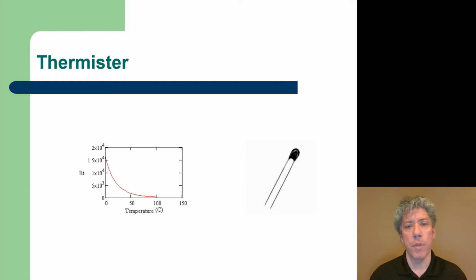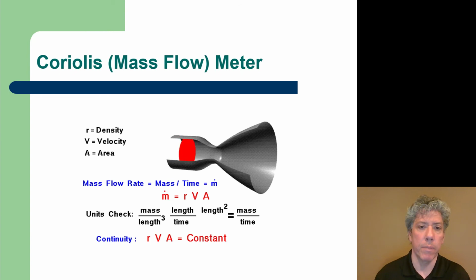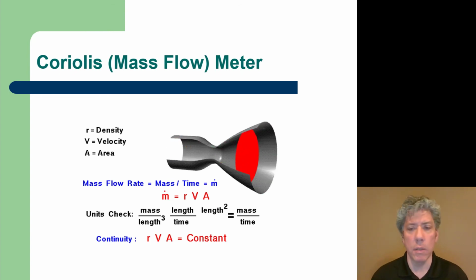There are also thermistors. Now, these are commonly used for sensing reference junction temperatures. They are nonlinear in the sense that their resistance does not vary linearly with temperature like an RTD does. But as long as you can calibrate it and keep a calibration curve, then you can measure the resistance of the device and back calculate the temperature. There are many other types as well. There are many different semiconductor types.